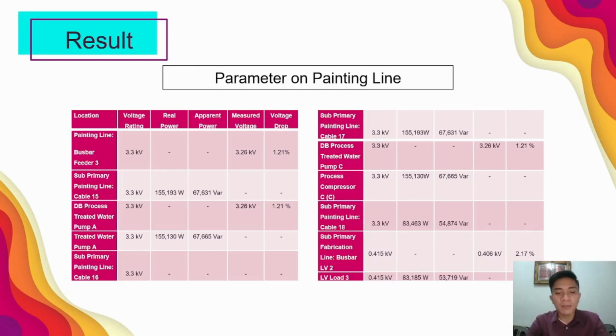Then both treated water pump A and process compressor C obtain the same apparent power, 67,665 var, while the measured voltage at the busbar feeder 3 is 3.26 kV along with the percentage of voltage drop of 1.21%. The same goes for the measured voltage and the voltage drop percentage of the DB process for both treated water pump A and pump C. Last but not least, the SPDB fabrication line busbar LV2 brings along 2.17% of voltage drop with 0.406 kV measured voltage.